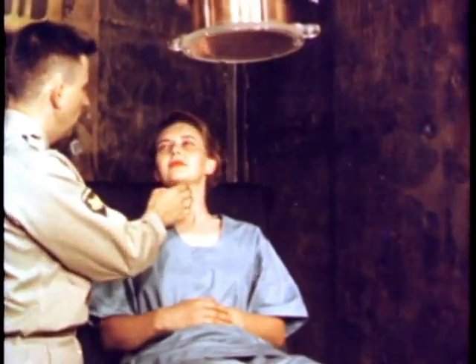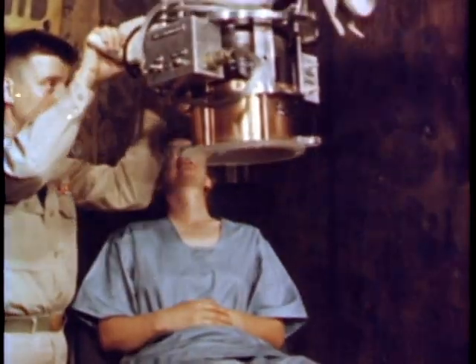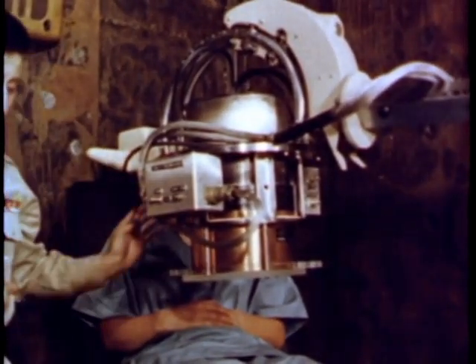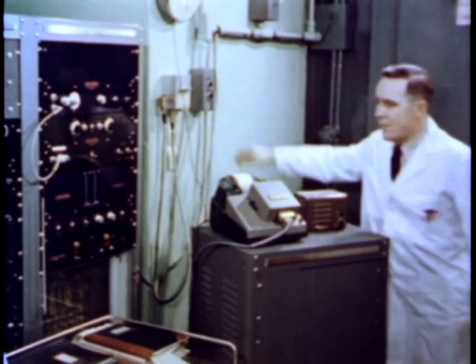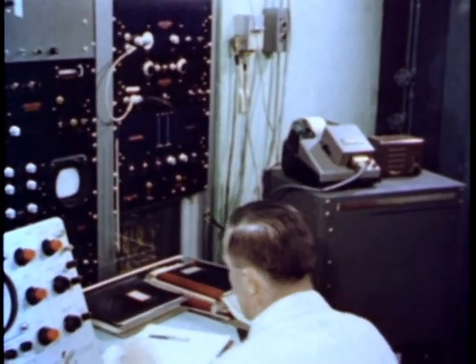To accommodate the eight-inch crystal phototube assembly, we have modified a medical fluoroscopy stand. This permits sufficient mobility to position the crystal so that an adult patient can be included in the field. Analysis of the data will permit both qualitative and quantitative interpretation.